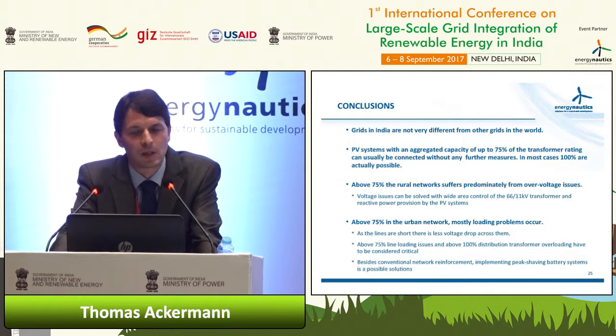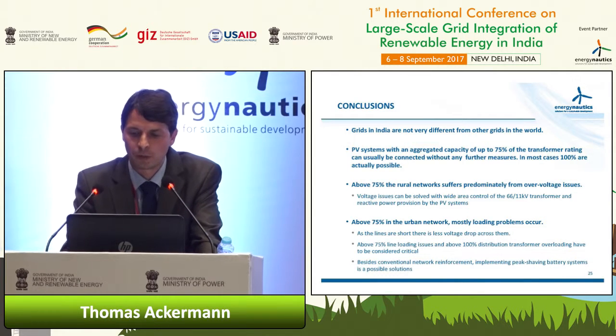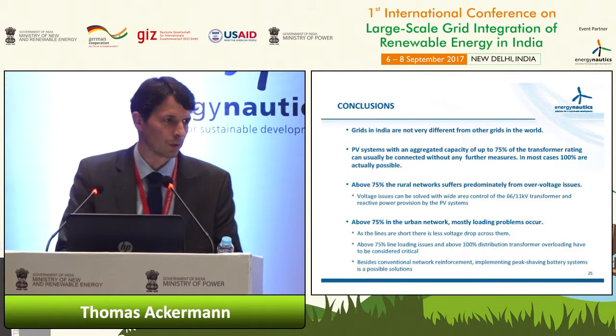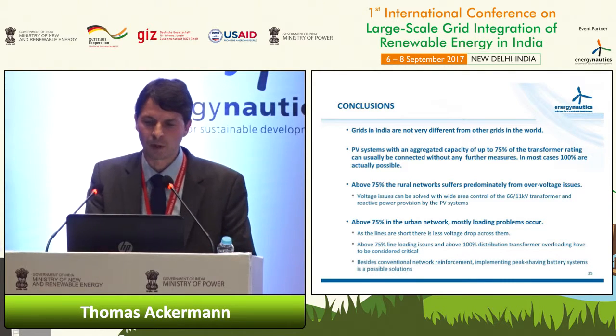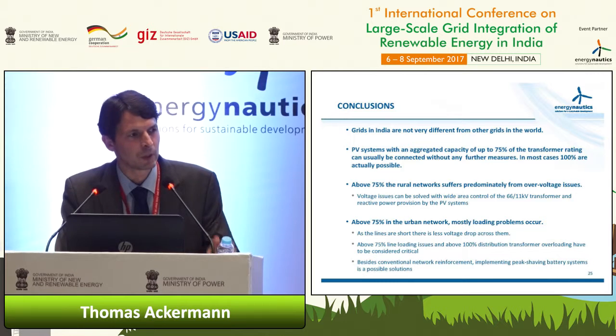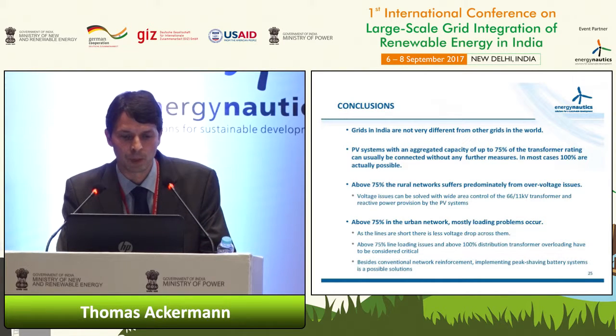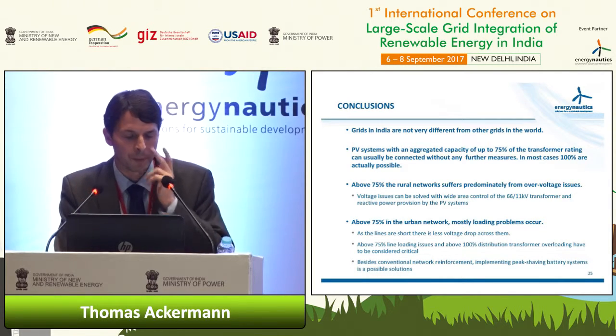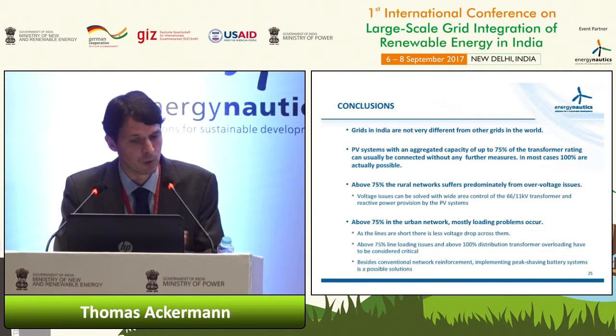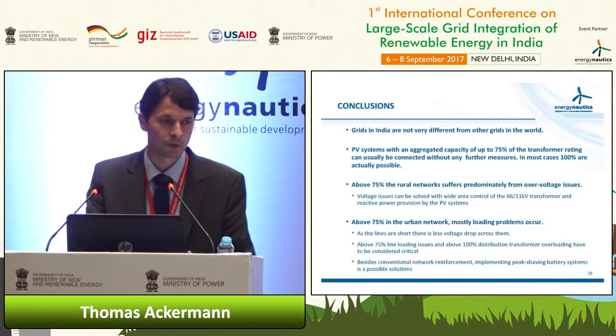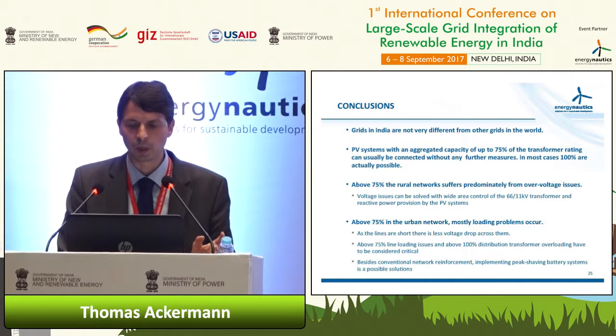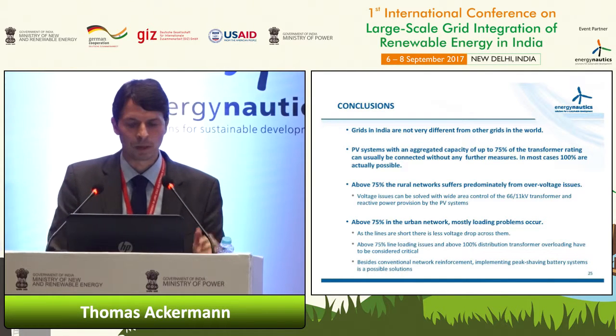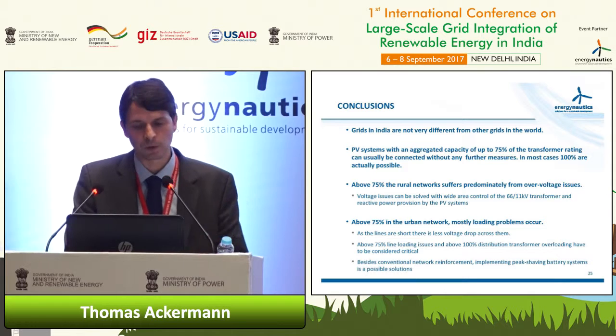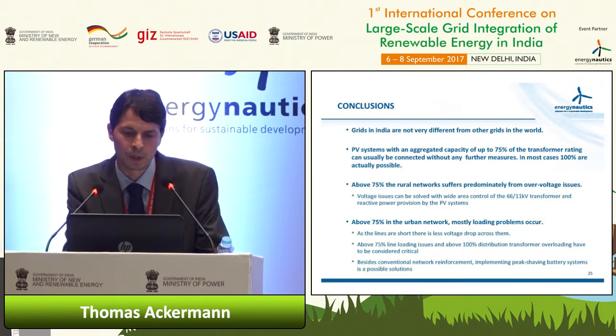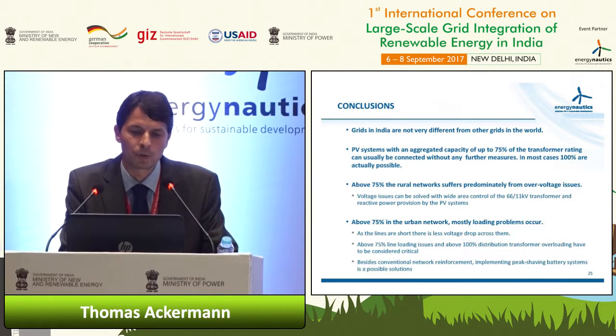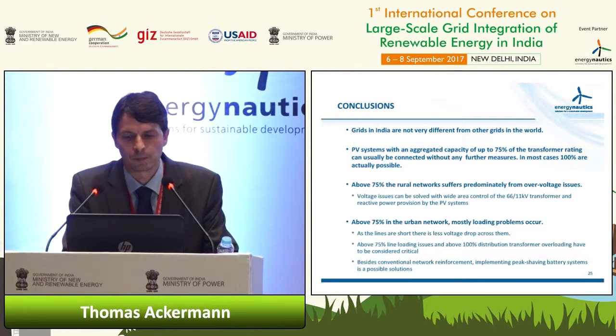What you can see is that up to 75% of the transformer rating, we usually have no issues at all with integrating. So phase 0 kind of up to 75%. And in many, many cases, actually 100% are possible. If we go above 75% in rural networks, we get overvoltage issues. This can be solved by using reactive power, for example, or wide area control. And in urban networks, typically, we have rather loading issues where we need to go into peak shaving batteries or PV capping.